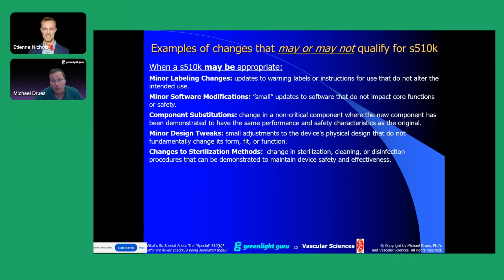Well, if you're updating a warning label, or modifying what I call low-level labeling, your instructions for use, not your indications for use. This is instructions for use. As long as they don't alter the intended use, and as long as they don't alter the indications for use, then you can make some small labeling changes.